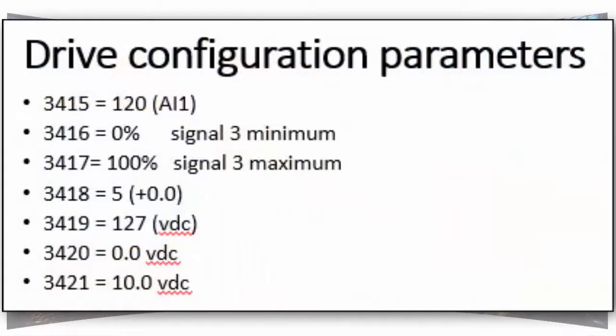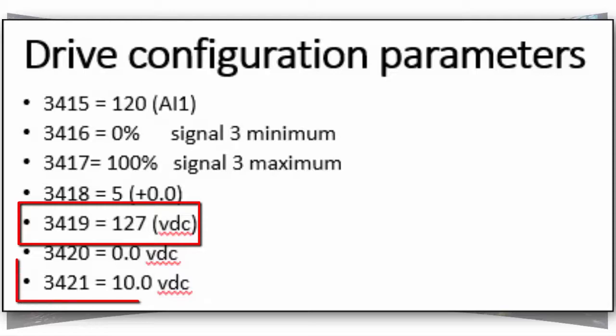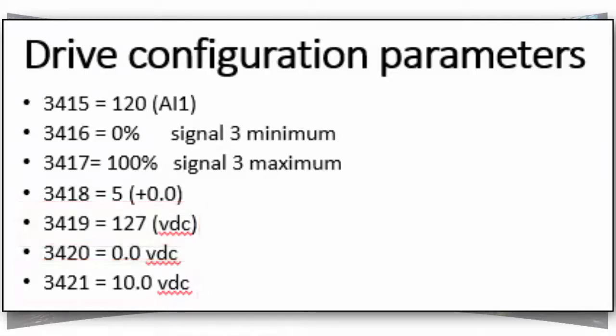Here's a list of the associated parameters for line 3. All we are concerned with is 3419, which will be changed to 127 which is VDC, and 3421 will be changed to 10 volts DC.